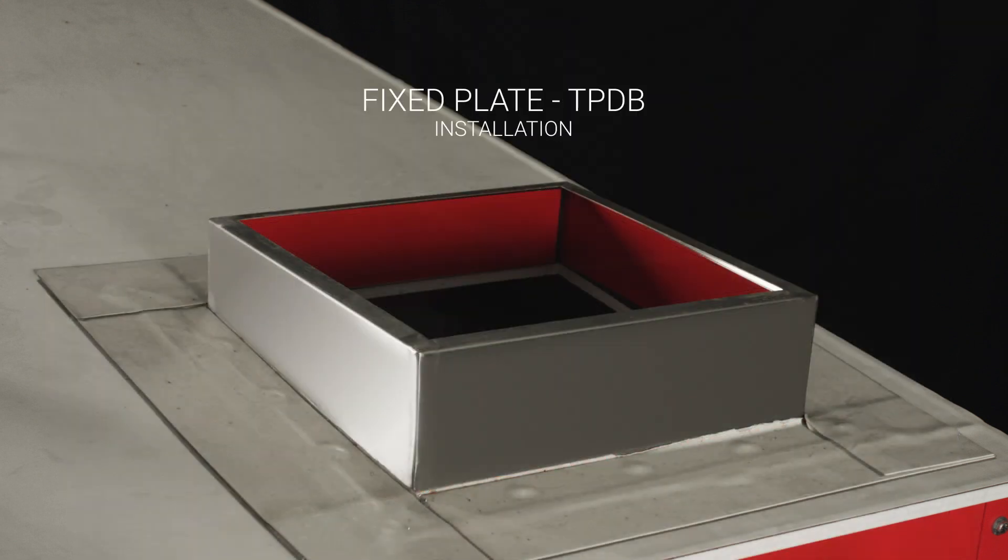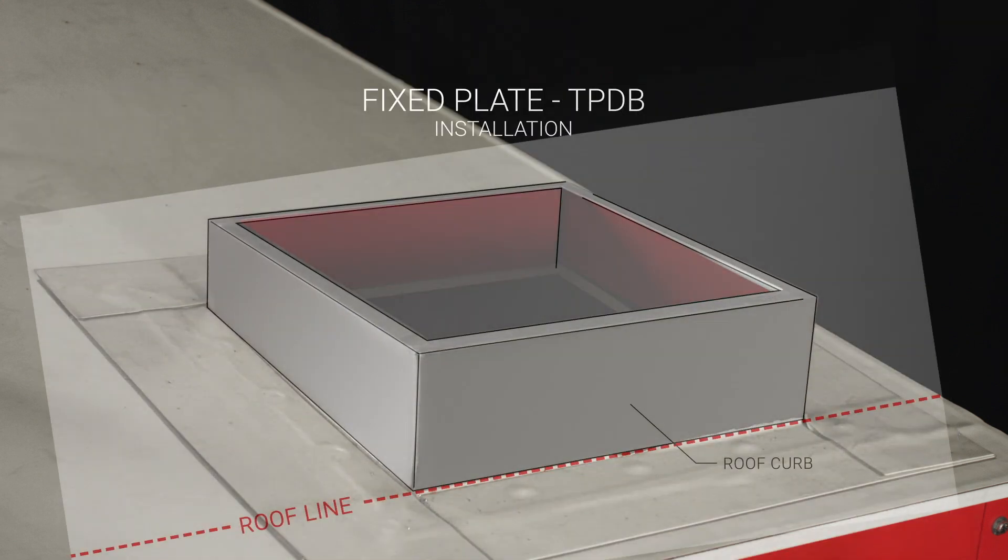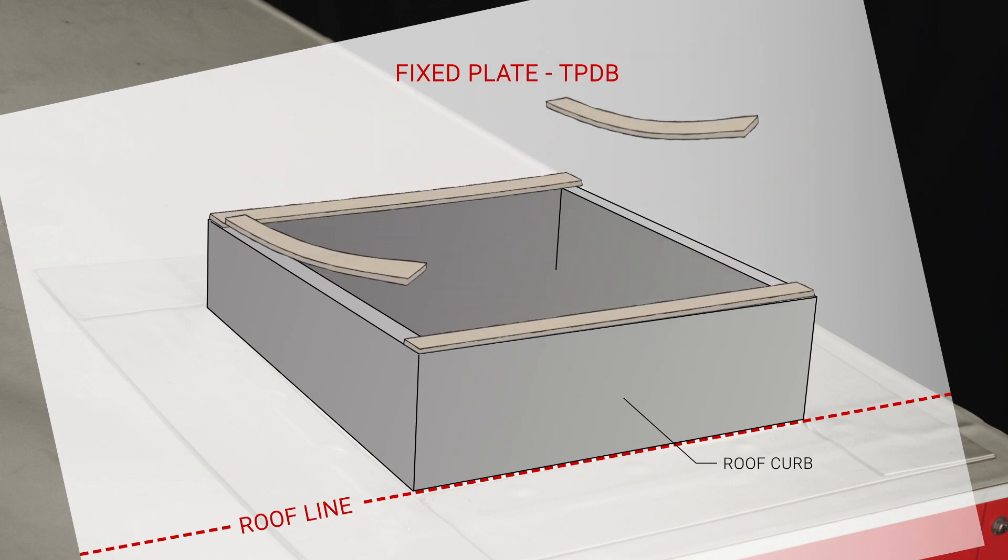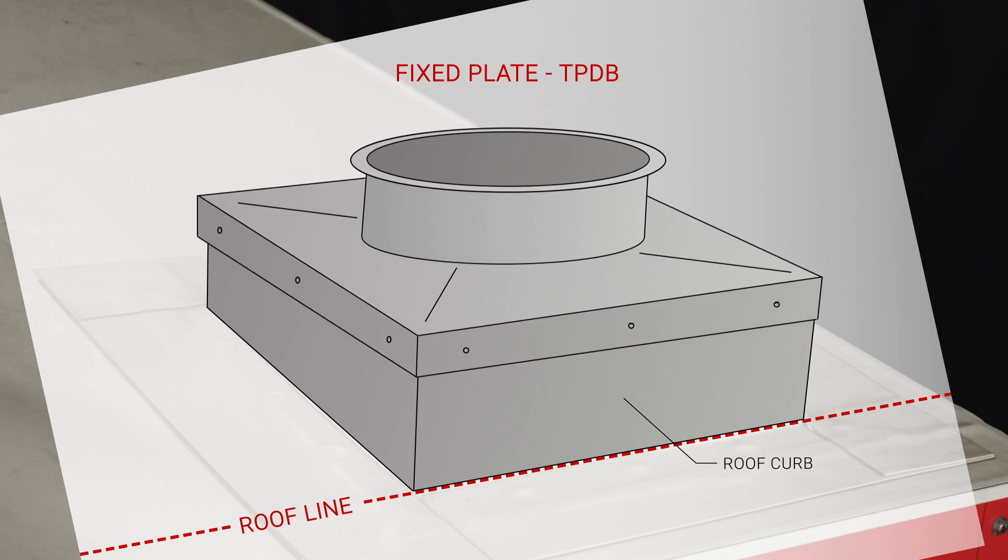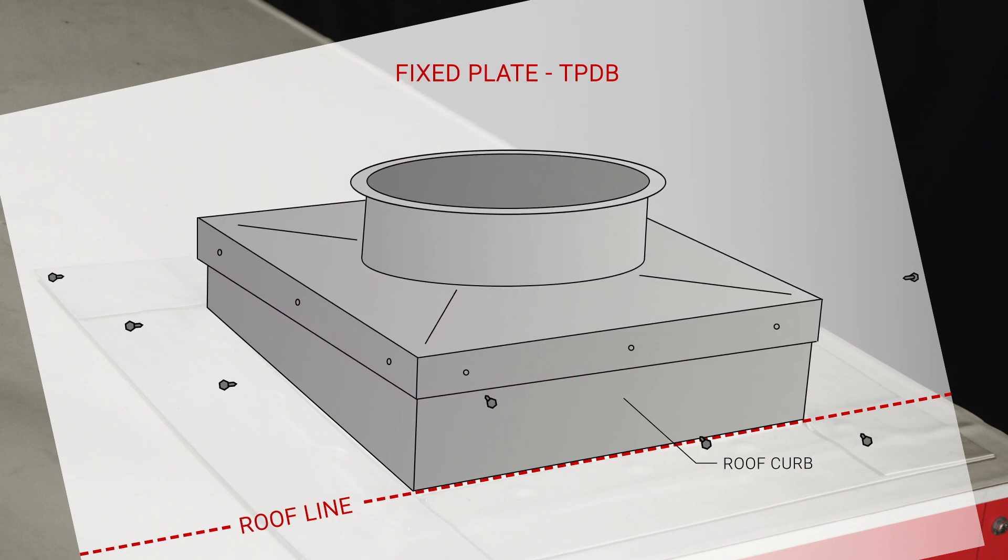To install a fixed TP DB plate, you must first add gasket material to the edges of the top of the curb as shown. Then set the transition plate on the curb. Lastly, secure the plate to the sides of the curb using three self-drilling fasteners per side.